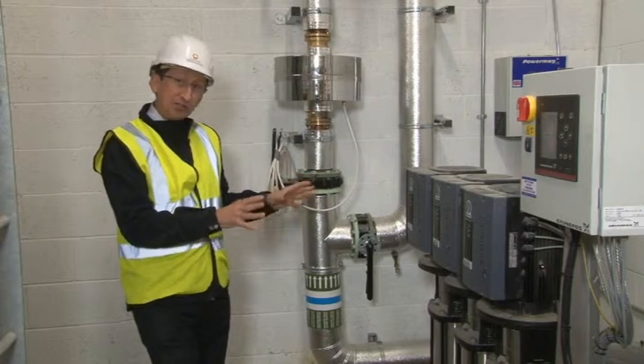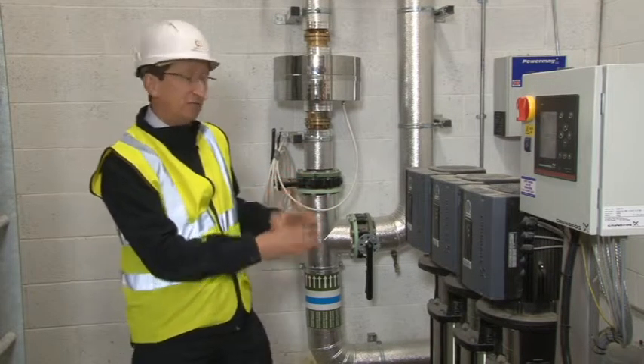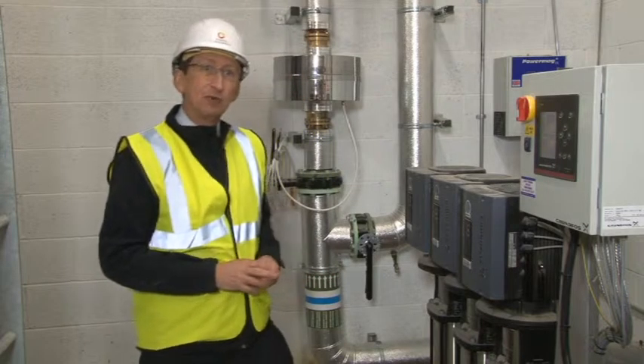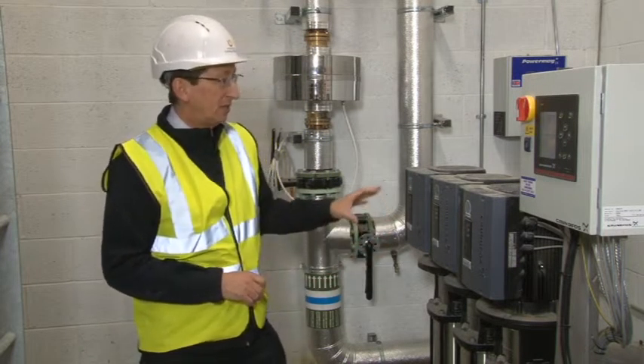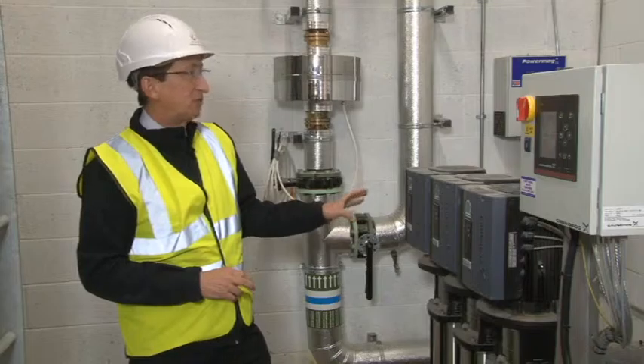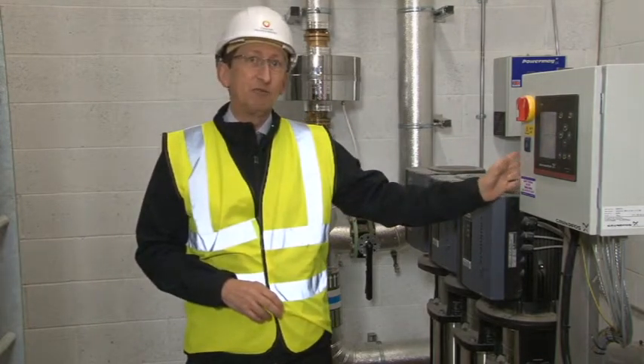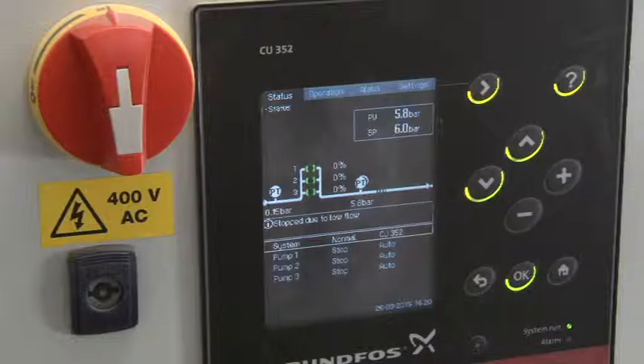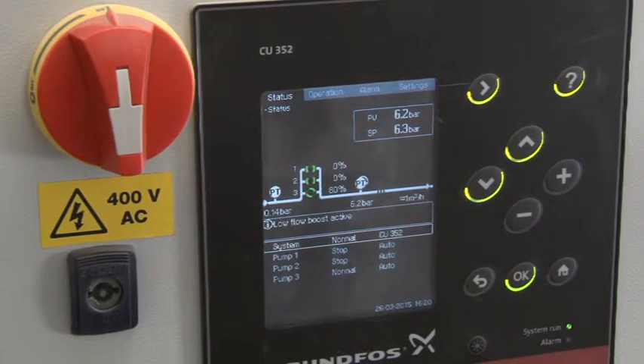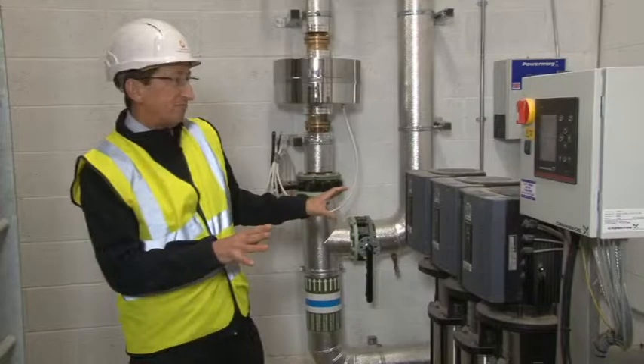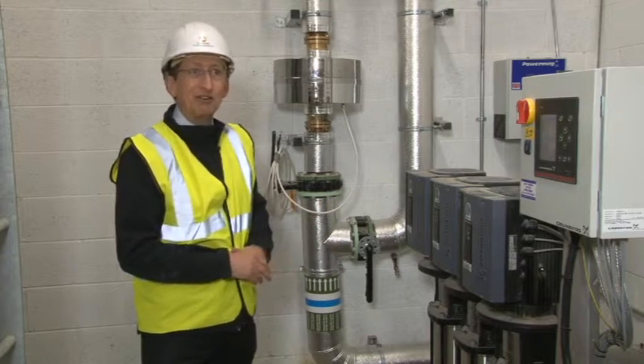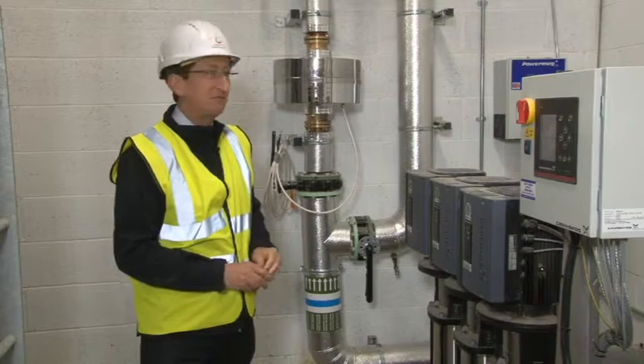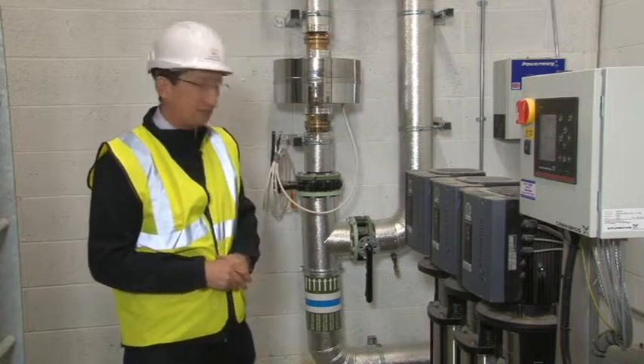I've obviously got some redundancy there as well, so if one did break down, there's still pumps to run to keep that water supply going out to the properties. If there is a problem with these pumps, then the control box here will send a signal back to the BMS to give us an alarm signal to say there's a fault on the system here. They could then come and look at the panel on the unit there and see which is the pump that's gone into fault. Shouldn't be any regular need to come and look in this area. It should sit there doing its job automatically until such point as a service is required.